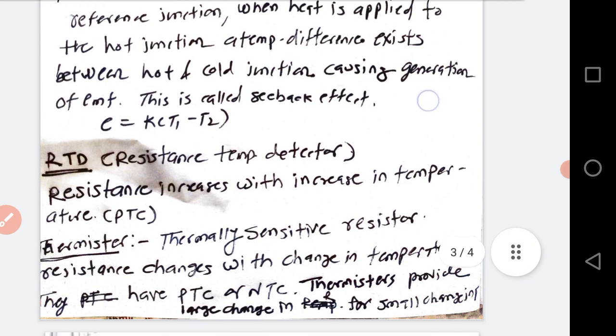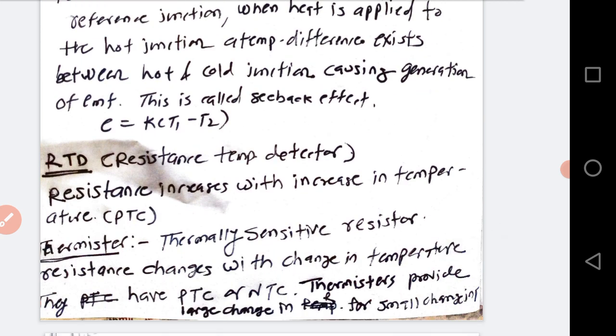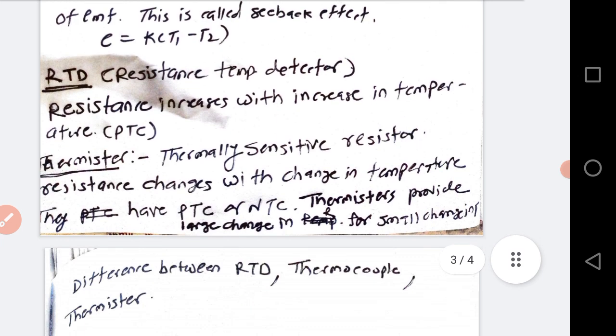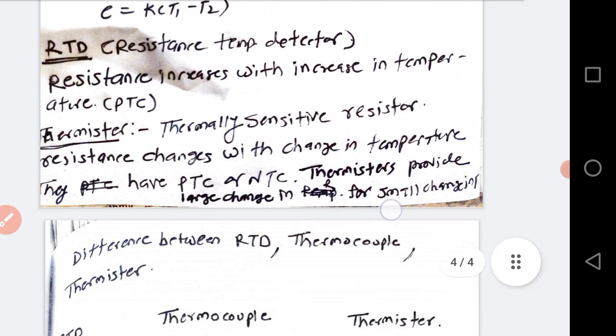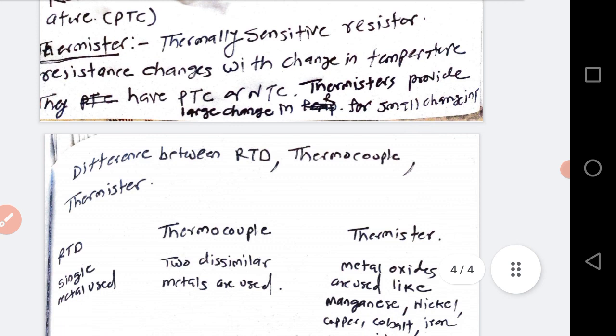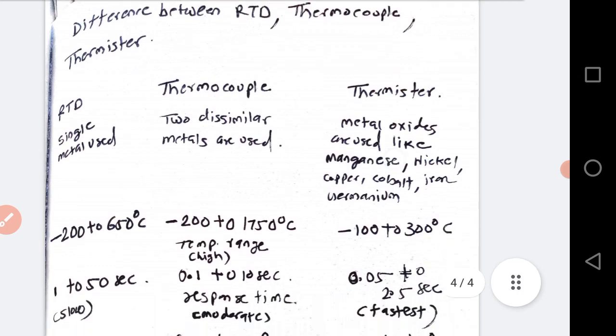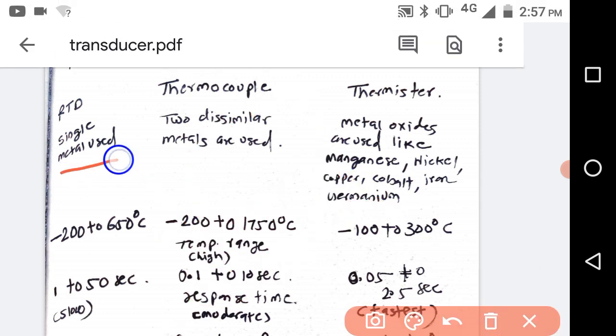What about RTD and thermistor? Here in RTD and thermistor, with respect to the temperature, their resistances change. RTD is resistance temperature detector and thermistor is thermal resistor or thermally sensitive resistor. Let us see the difference between RTD, thermocouple and thermistor. So in RTD, single metal is used. In thermocouple, two dissimilar metals are used. In thermistor, metal oxides are used like manganese, nickel, copper, cobalt, iron, germanium.